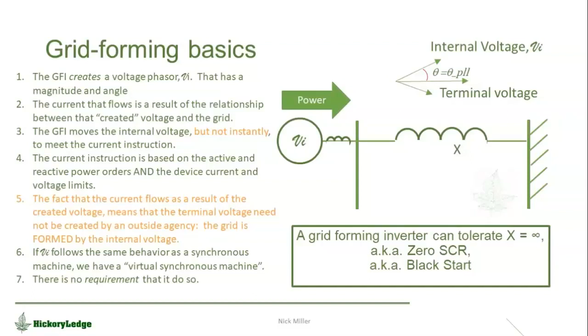One of the things we need to worry about, and the industry hasn't fully gotten its head around, is that grid forming inverters, just like grid following inverters, have limits on the current they can inject. Synchronous machines do as well, but the current limits of converters are much harder. Harder means if you violate the current limit, you've got to fix it really fast. Synchronous machines with lots of iron and copper are quite tolerant of very high currents, and they have no mechanism directly to control their current. So if you overcurrent a synchronous machine for too long, it will trip, but it doesn't have the mechanism to throttle back the current. Whereas inverters can take action on VI to bring the current back under control, or they can just say, we ain't doing it.